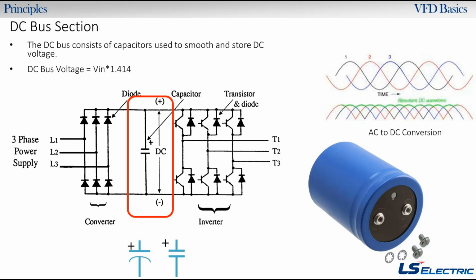And it's the same thing on the drive. If you load up the outside of the drive, you're more susceptible to voltage imbalance, and that DC bus could be bouncing around because you're really pushing that drive.